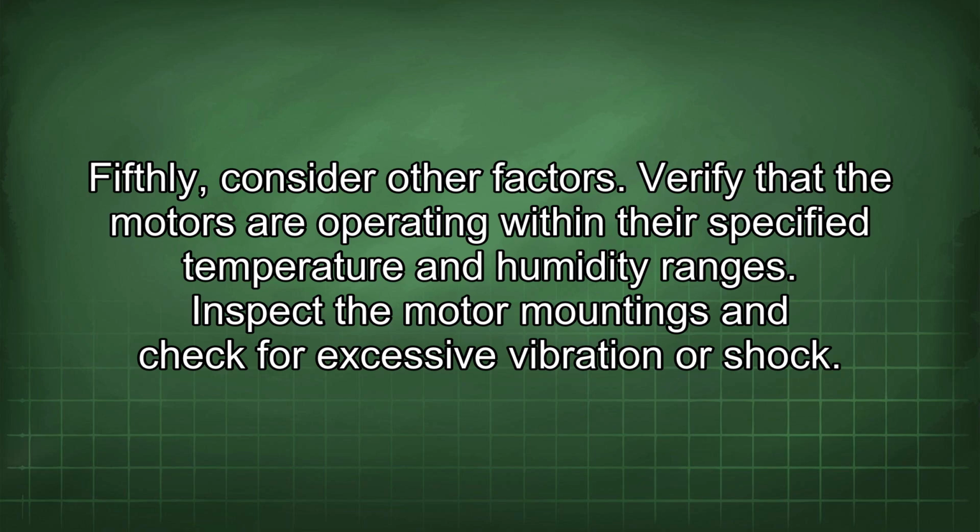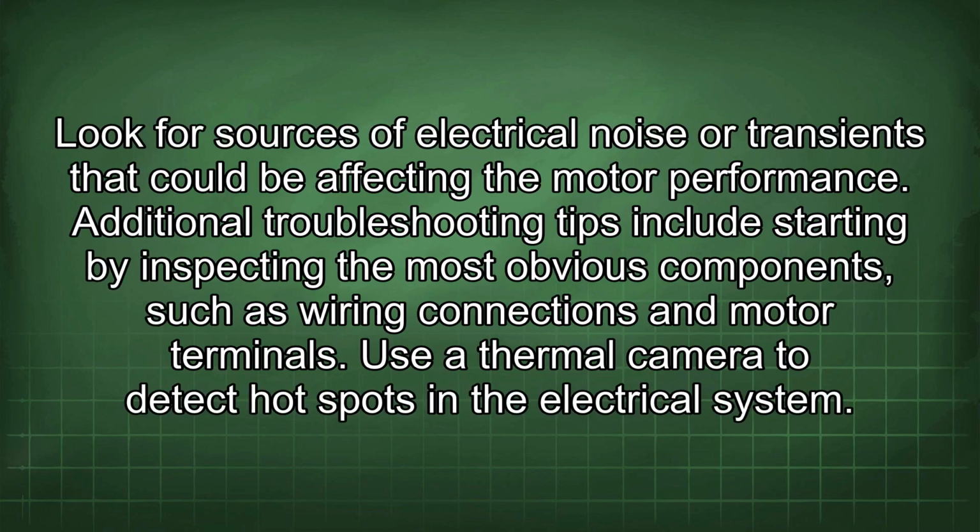Fifthly, consider other factors. Verify that the motors are operating within the specified temperature and humidity ranges. Inspect the motor mountings and check for excessive vibration or shock. Look for sources of electrical noise or transients that could be affecting the motor performance.